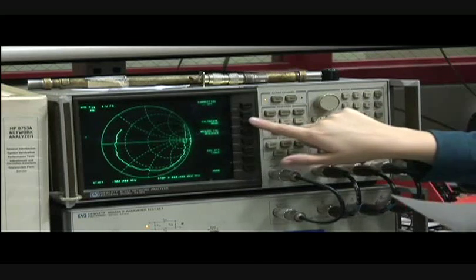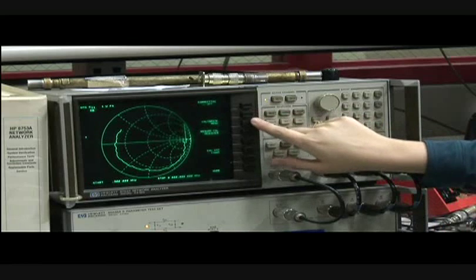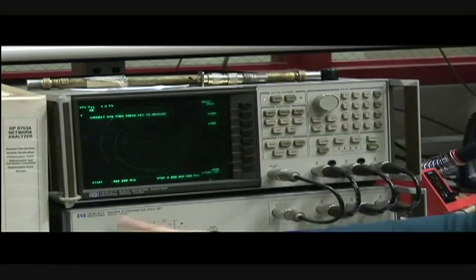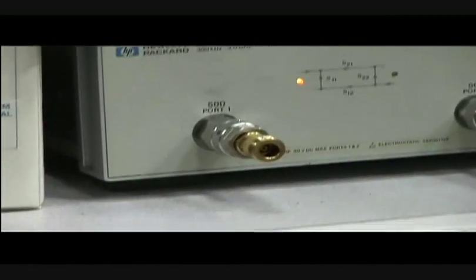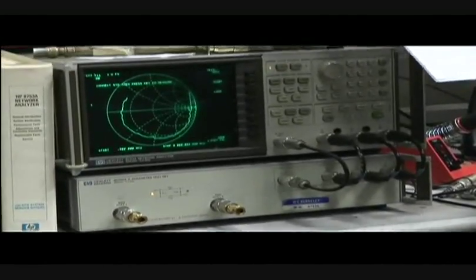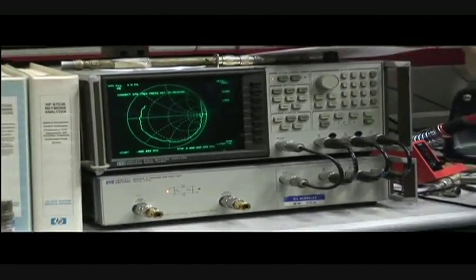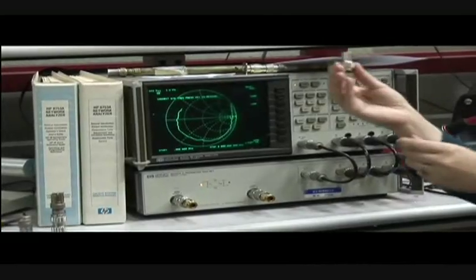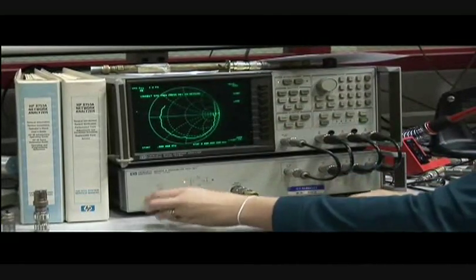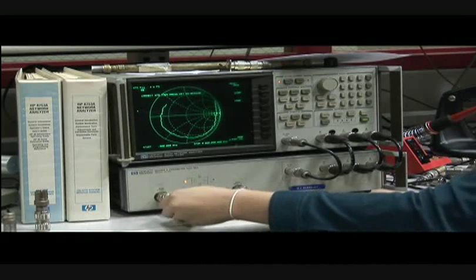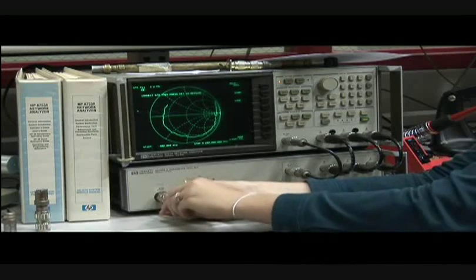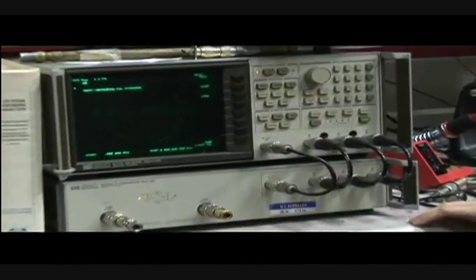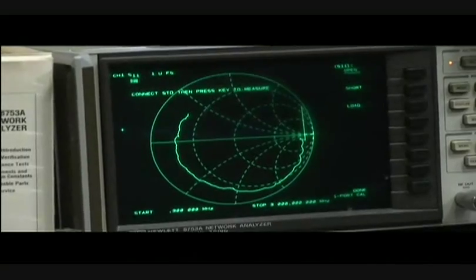Calibrate menu and then S11. This is the S11 port here and then you're going to connect your open short and loads to the port and hit the appropriate button. So first I'll connect the open which is this, just screw it on right here and then you press the open button and there's a little beep when it's done.